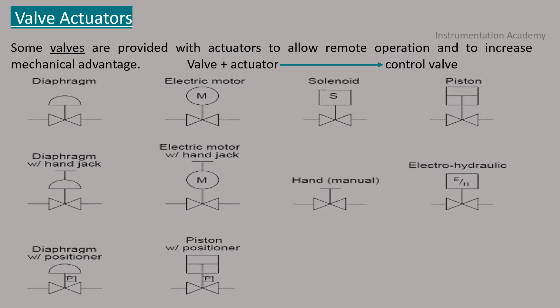Valve actuators. Some valves are provided with actuators to allow remote operation and to increase mechanical advantage. The combination of a valve and an actuator is commonly called a control valve. Control valves are symbolized by combining the appropriate valve symbols and actuator symbols. This figure shows the P&ID symbols for the common valve actuators. Although each is shown attached to a gate valve, an actuator can be attached to any type of valve body. If no actuator is shown on a valve symbol, it may be assumed that the valve is equipped with a hand wheel for manual operation.